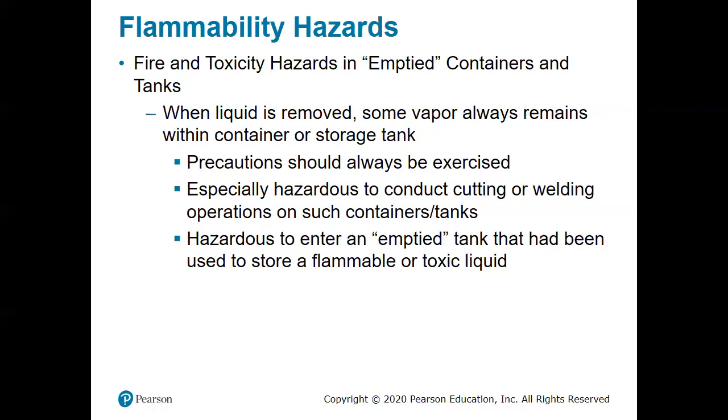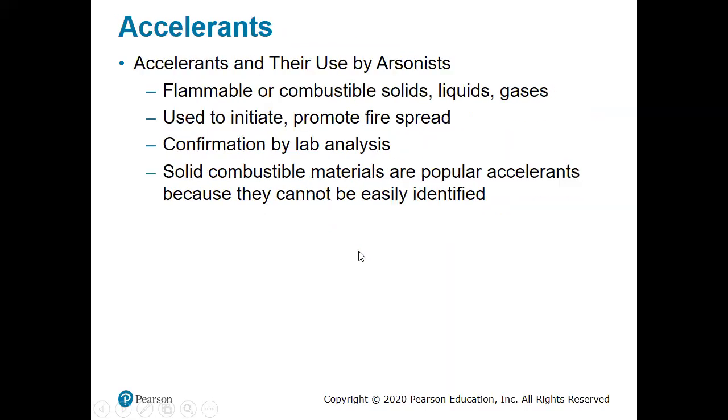It's going to ignite very, very quickly. And when things ignite, they create tons of gas, and tons of gas contained in a small space is a bomb. You don't want to do that. So make sure that you are dealing with things cautiously. And remember that no tank is ever truly empty. It just means that all the liquid's gone. You still have to handle the part of emptying the vapor out before you do anything else to it.